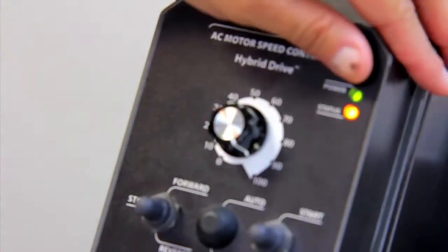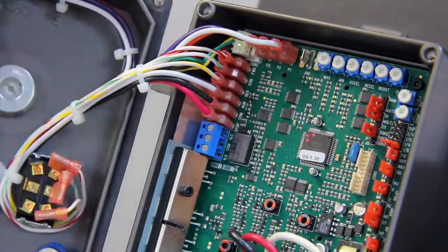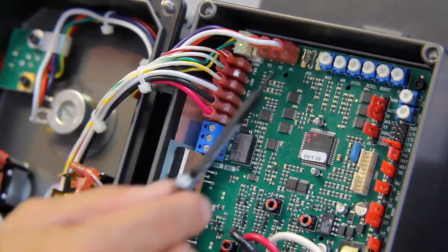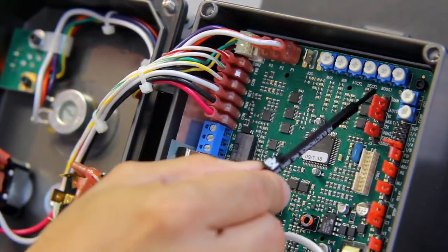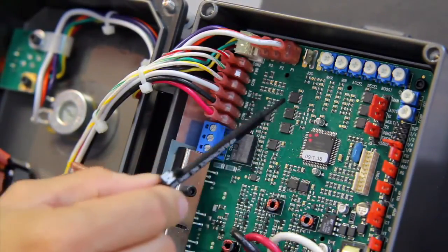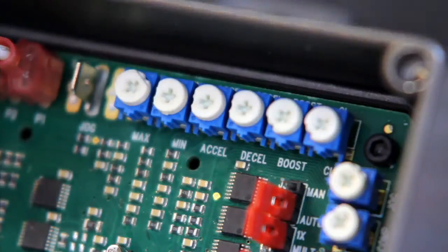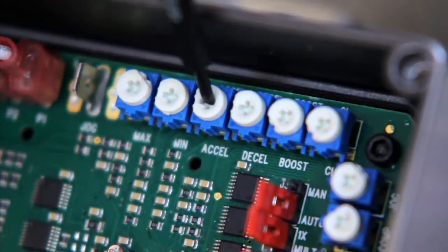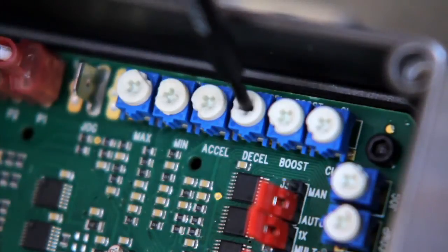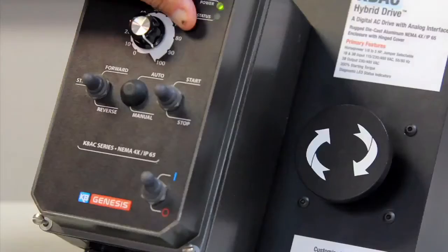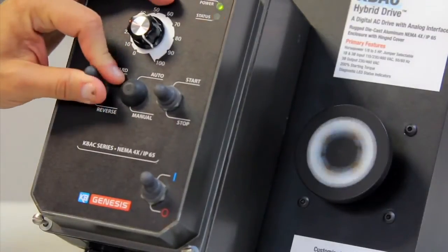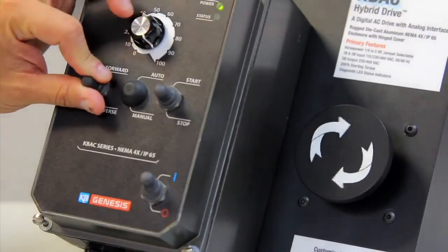It is simple to adjust any of the drive's trim pot controls. In this demonstration, we will adjust the acceleration and deceleration of the drive. Adjust both trim pots to the minimum position by turning them counterclockwise. The motor will now operate with rapid acceleration and rapid deceleration.